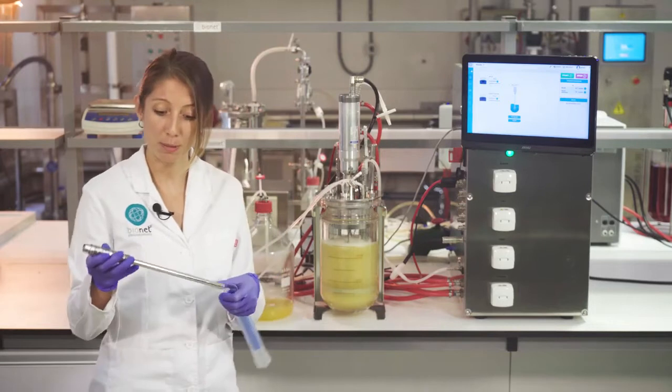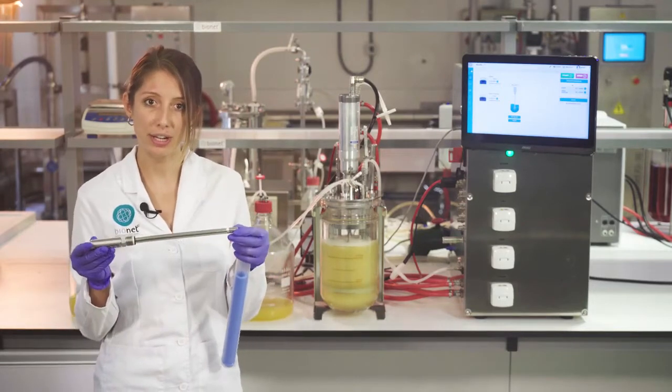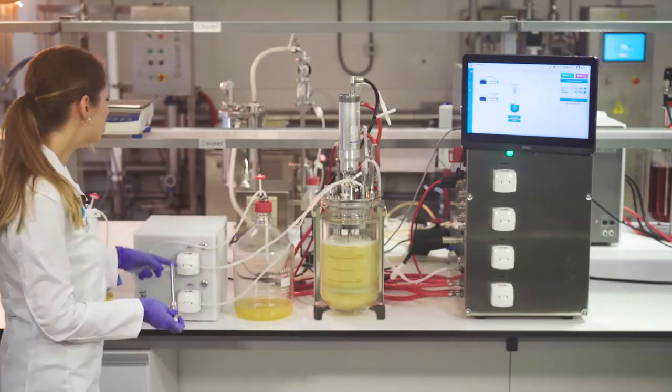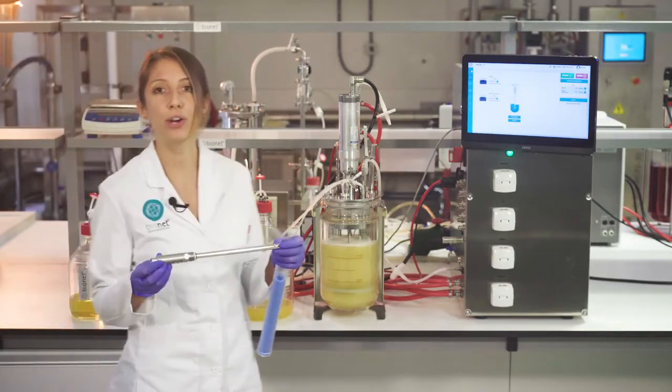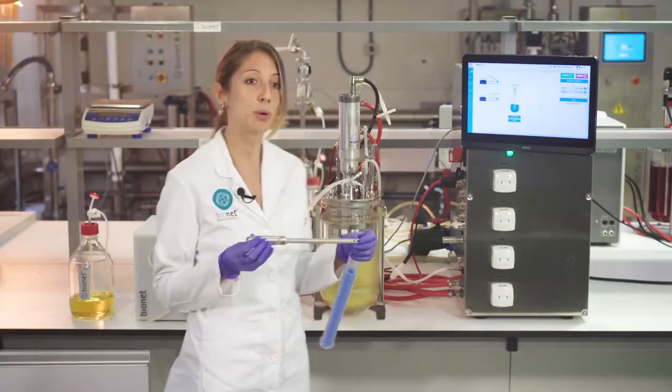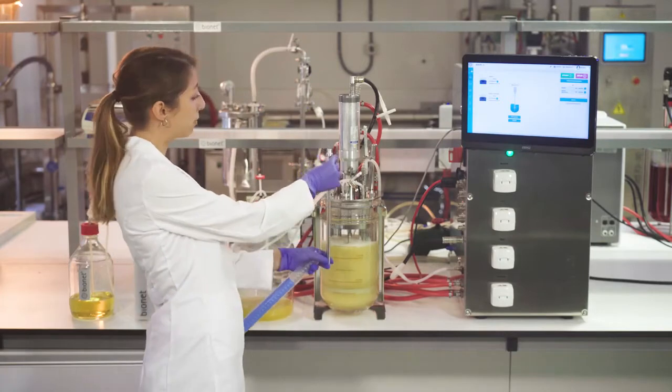For example, if you had an optical density sensor like this one here, the addition and withdrawal pumps could be both configured to respond to the measurements of this sensor, that would be introduced into the vessel through the ports and connected to the VCU following the plug-and-play concept.